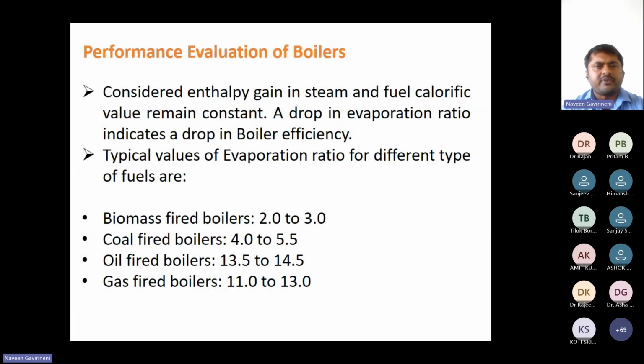So these are the performance evaluation of the boiler, enthalpy gain. I have already explained. This is 4 to 5, 5.5. This is the evaporation ratio range. Different boilers have different evaporation ratios.